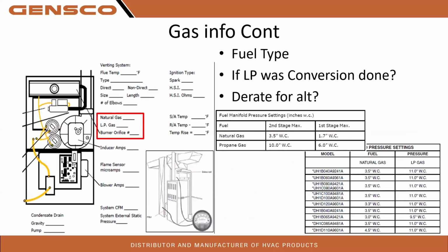Okay, so of course we want to know what fuel type. If the LP conversion was done, was it derated for altitude? These are all important. This is very important information to put on. So we have natural gas or LP. You can check either one. Of course, what orifices are in it, right? Depending on your derate or what you're trying to do, you may have to change spuds, right? You may have to set the gas valve differently, depending on what kind of derate you're trying to get done. So if you derated with spuds, we're going to want to know that. We're going to want to notate that. It went from 53s to 56s or whatever that looks like.